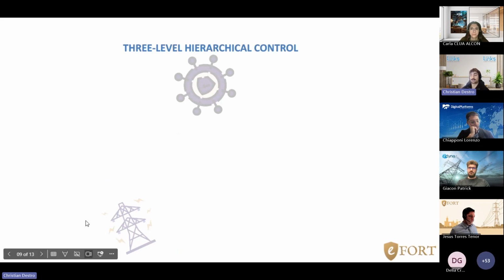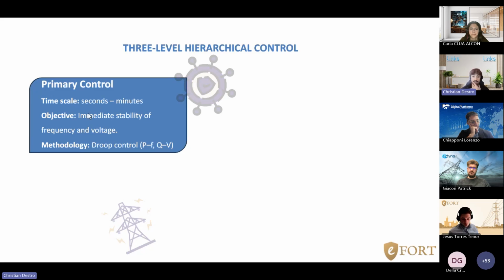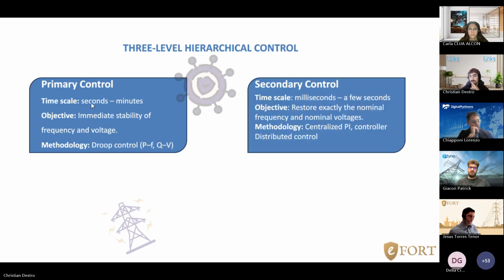The most widely adopted model is islanded microgrids. In the three-level hierarchical control structure, we have primary control, timescale milliseconds to a few seconds. The objective is immediate stability of frequency and voltage, methodology droop, power-frequency and reactive power-voltage, where frequency is regulated through active power and voltage through reactive power.